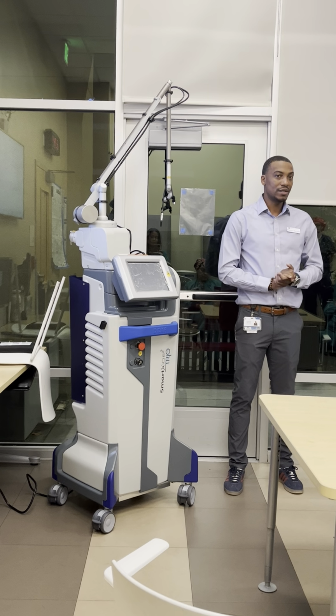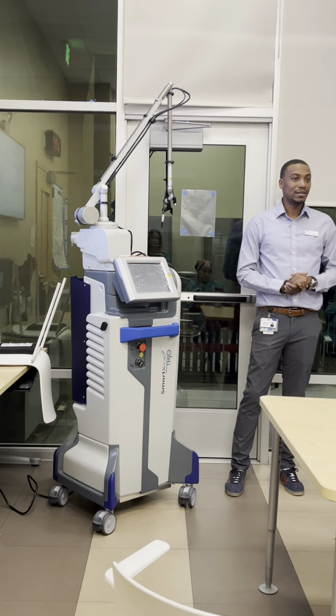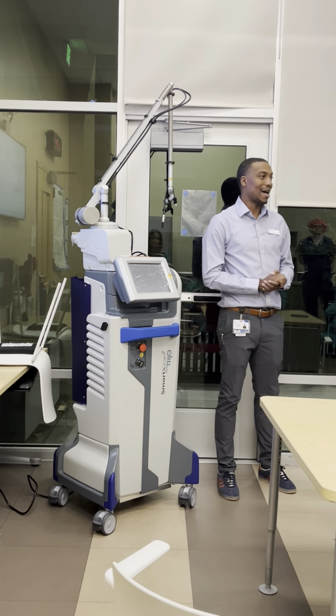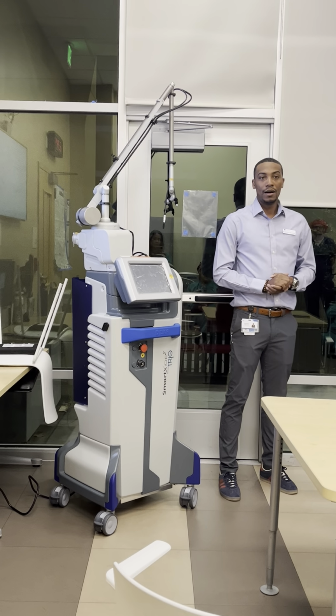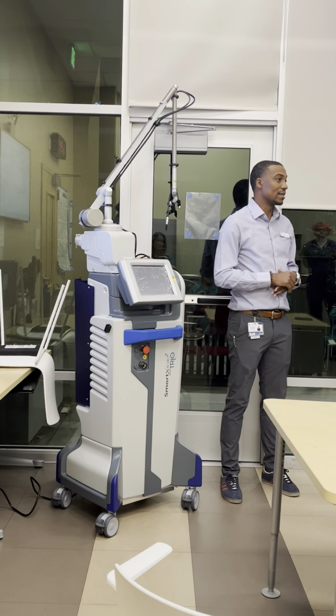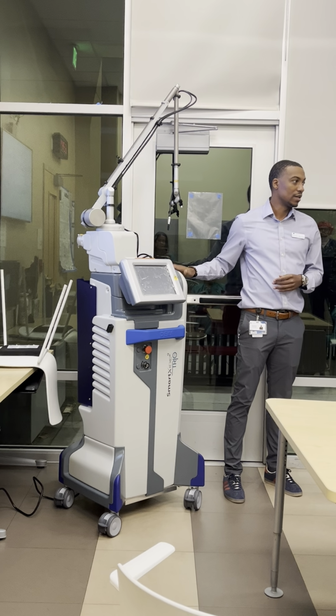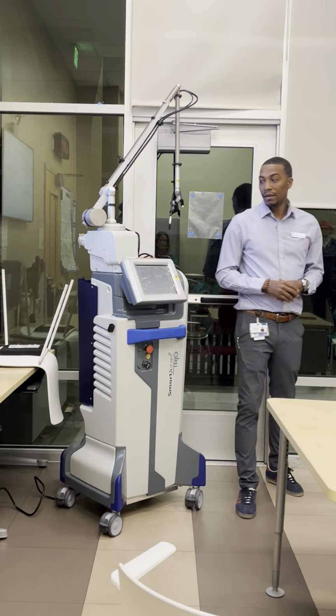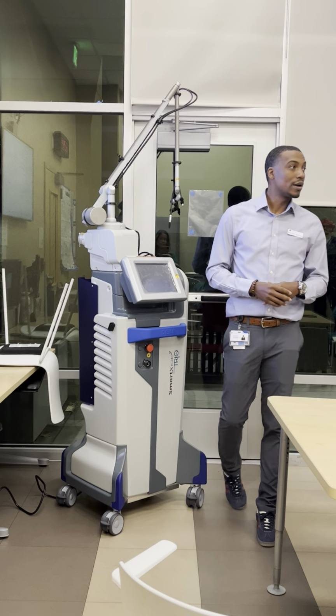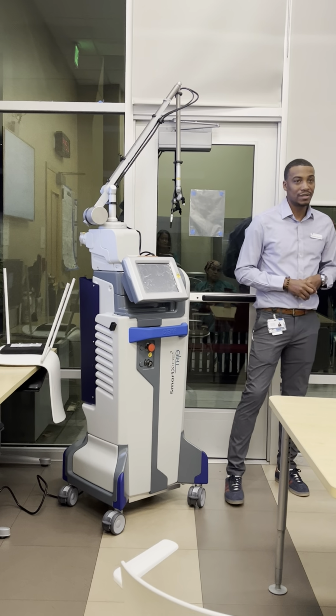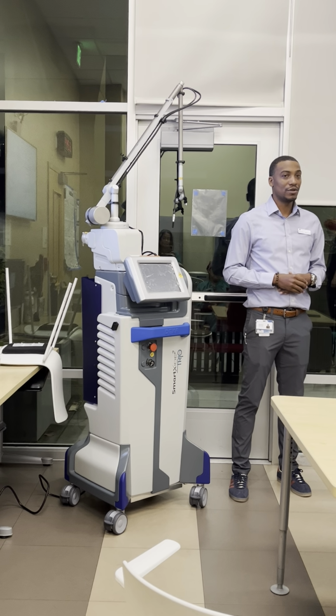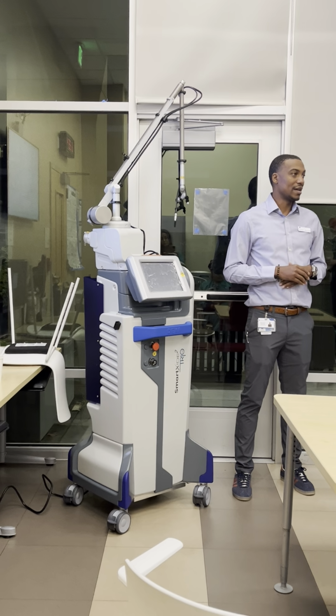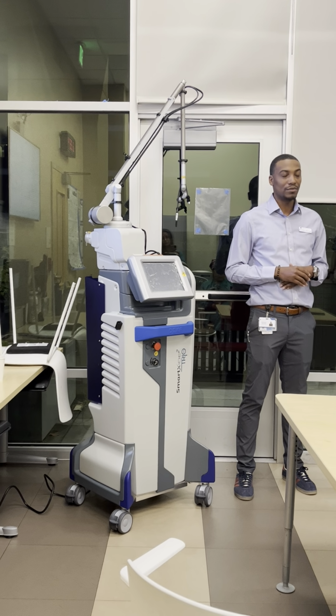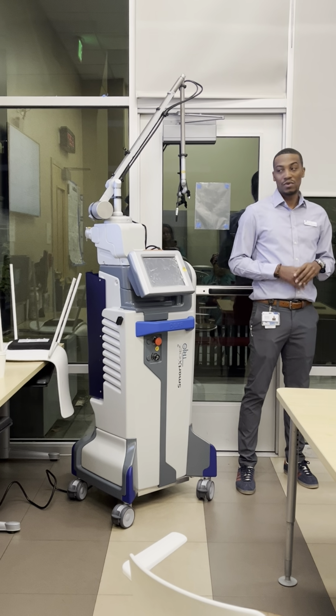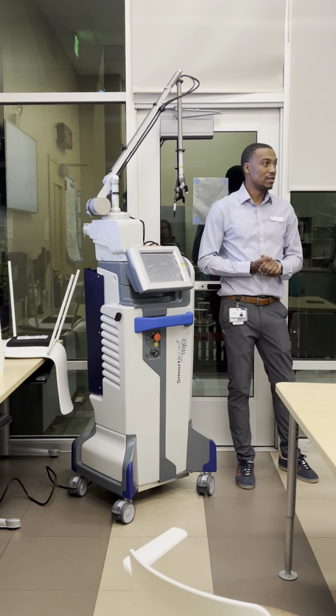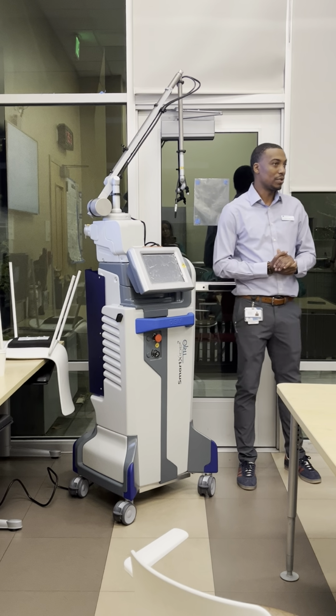CO2 wavelength is 10,600, infrared. Not necessarily dangerous as far as an ocular safety hazard, but it does high thermal damage. That being said, I see a lot of reading glasses in the room. Those do not protect you from the laser. That's a common misconception. Even though this laser is absorbed into glass and water, your reading glasses don't have enough optical density to stop what's called the blink aversion reaction. Our aversion reaction to bright lights being flashed at our eyes is about 0.25 to 0.5 seconds. Your reading glasses won't stop it. The glasses provided with your laser have an optical density of 4+.